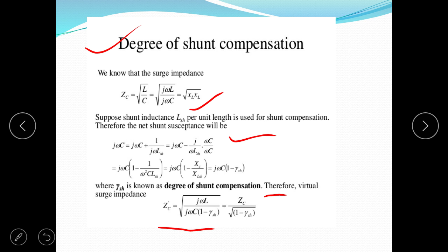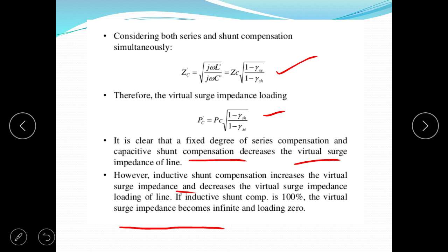Now considering both series and shunt compensation simultaneously, we obtain ZC dash is equal to ZC root of (1 minus gamma SE) divided by (1 minus gamma SH). Therefore, the virtual surge impedance loading, the SIL loading, PC dash is equal to PC root of (1 minus gamma SH) upon (1 minus gamma SE). So it is clear that a fixed degree of series compensation and capacitive shunt compensation decrease the virtual surge impedance of the line. However, inductive shunt compensation increases the virtual surge impedance and decreases the virtual surge impedance loading of the line. If inductive shunt compensation is 100%, the virtual surge impedance becomes infinite and loading 0.